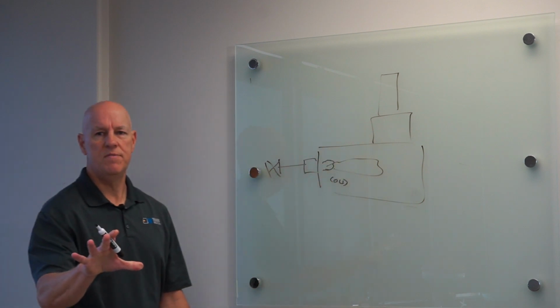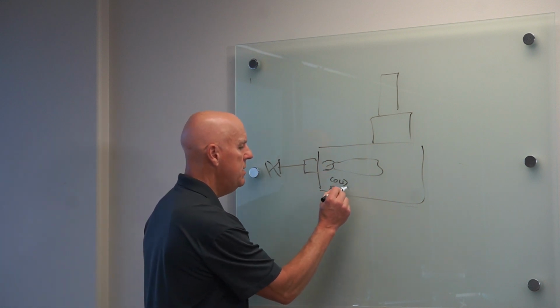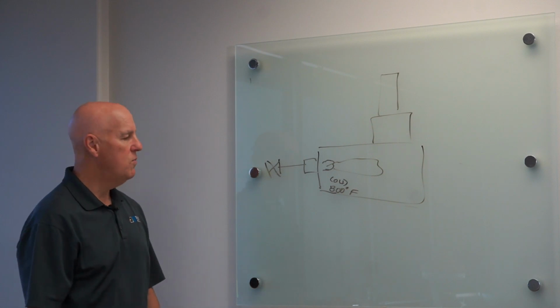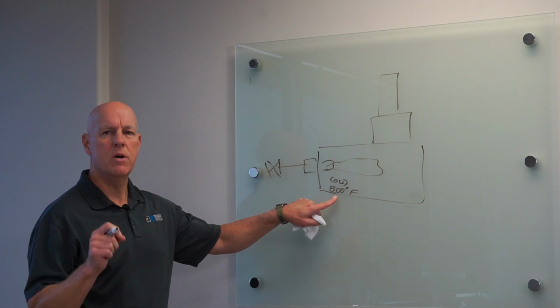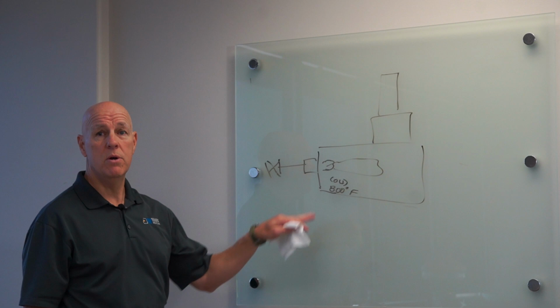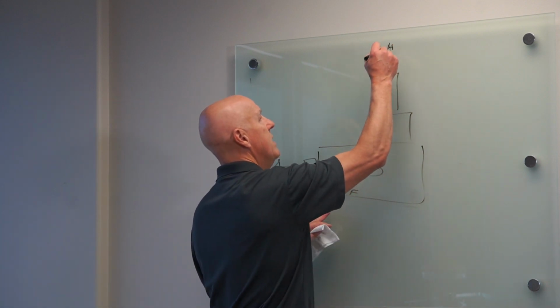And cold is a relative term. Let's say it's 800 degrees. Maybe you think that's not very cold, that seems really hot to me. Well, at 800 degrees, the problem is I don't burn the carbon monoxide in that environment. If I don't burn the carbon monoxide, where does it go? Well, it goes out the stack.